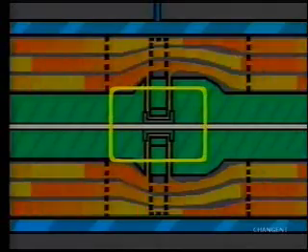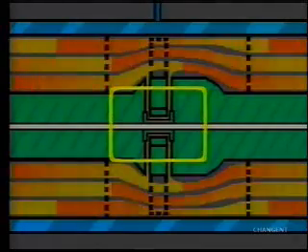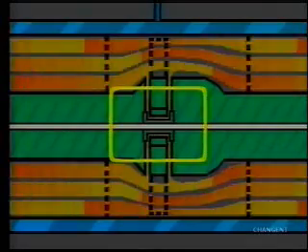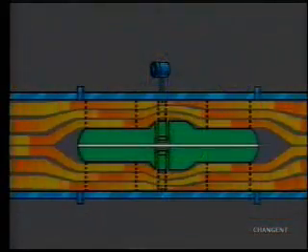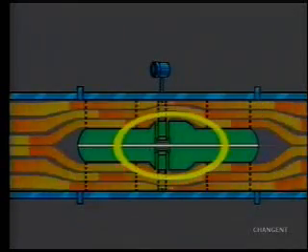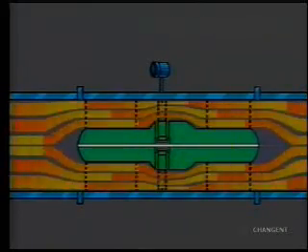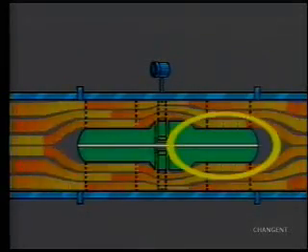However, to minimize the load on the bearing, the rotor also floats. Now, this floating occurs as liquid entering the meter is deflected outward by an upstream cone, which increases its velocity and causes a slight pressure drop. After passing the turbine blades, the flow is redistributed. Because the rotor hub is larger than the upstream cone, some of the fluid flows directly over the hub. The rotor then floats in balance between the upstream cone and the downstream cone.